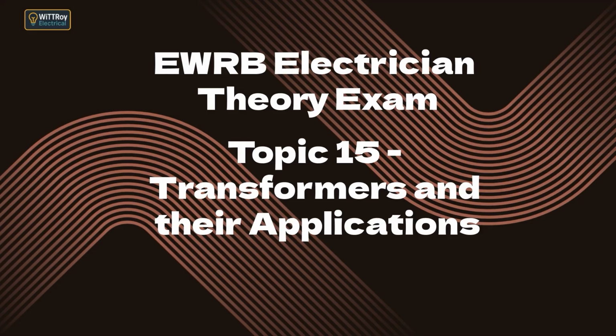15.3b Explain the term burden as it relates to current transformers. The burden is the total load connected to the CT secondary, including meters and wiring resistance. CTs are designed to operate accurately within a certain burden. If the burden is too high, the CT may saturate or give inaccurate readings. Understanding burden ensures reliable metering and protection.